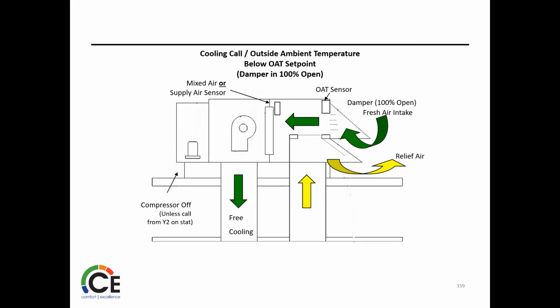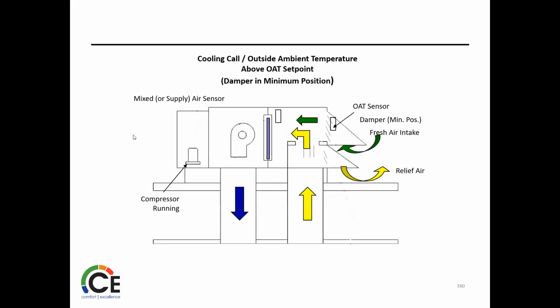Again, in this, you've got a mixed air or supply air sensor located there. You've got your outdoor sensor located. Dampers are 100% open, so we're pulling in all that fresh air. We're throwing the indoor air out, pulling in fresh air, operating through free cooling. So it's cold enough outside that we're just expelling the air from the building, and pulling in fresh air from the outside, going through the evap coil, getting down through the blower, cooling the space off. Compressors are off.